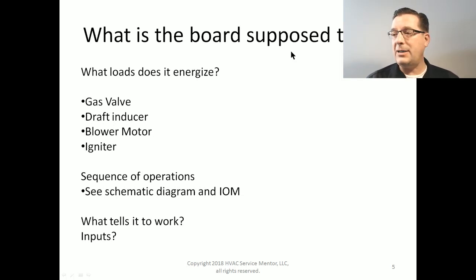Not only is it supposed to energize these things, it's also supposed to de-energize them at the right time. And this leads us into the sequence of operations. When you have a piece of equipment that is controlled by an electronic control board, the electronic control board is programmed with a sequence of operations. And the better you know what that sequence of operations is supposed to be, the better you're able to analyze how that control board is functioning, what it's supposed to do. Remember, the job of the electronic circuit board is to energize and de-energize specific loads in a specific sequence based on inputs and internal programming. So that sequence is based on its internal programming.